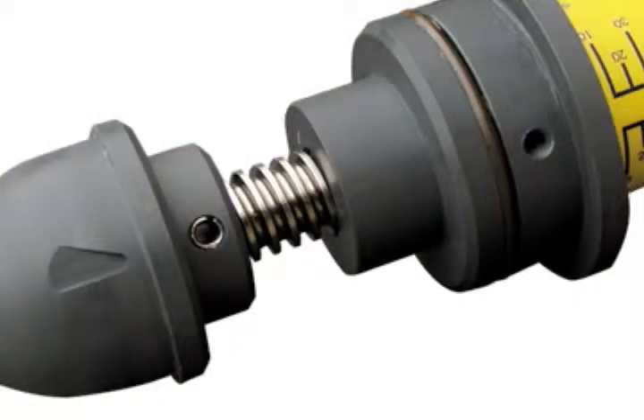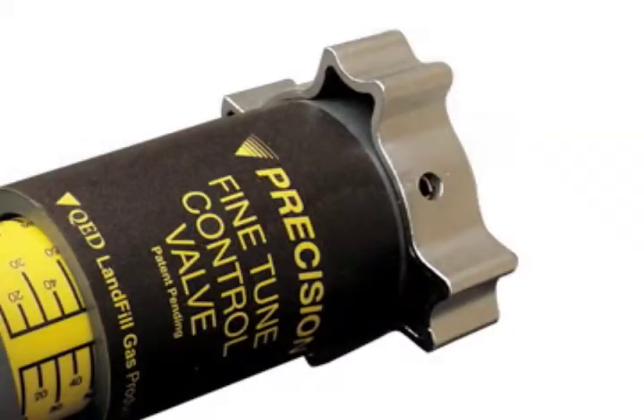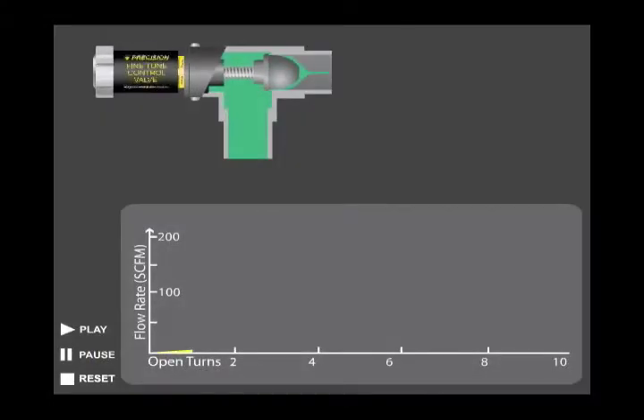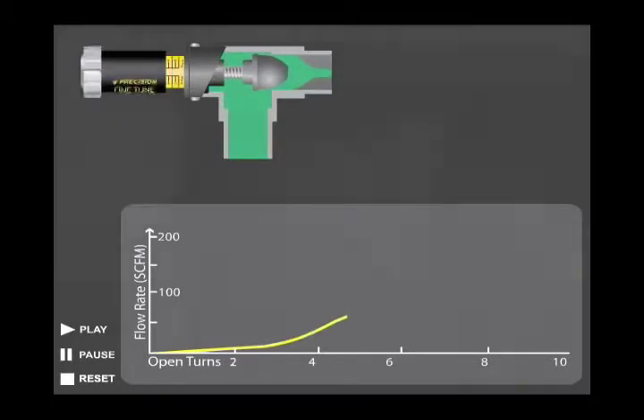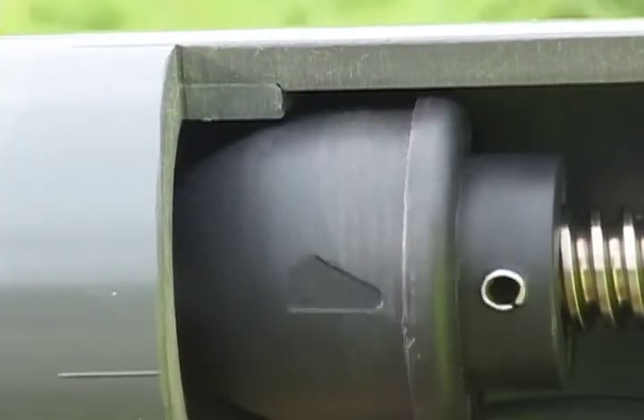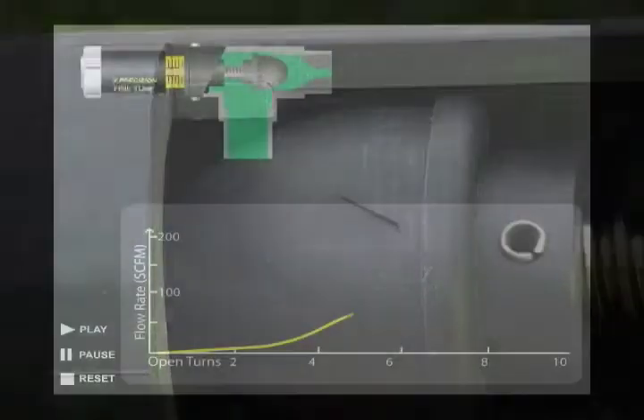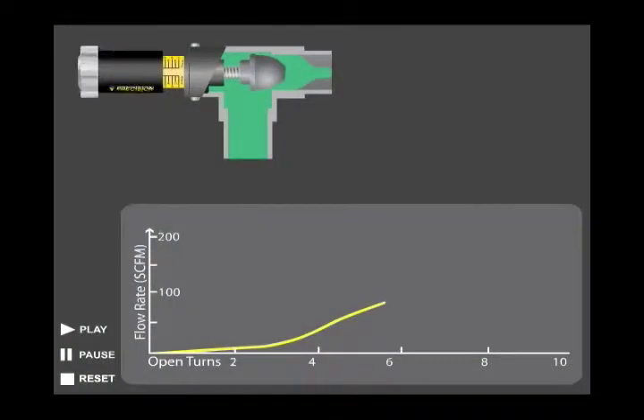The valve is constructed with a rugged stainless steel stem and handle, making it much more durable in harsh outdoor environments. The fine-tuned control valve's design gives you the ability to achieve linear flow adjustments across the entire range of valve movement. It uses a flow-tuned design valve plug, which allows for fine-tuning even at very low gas flow rates under 10 CFM.